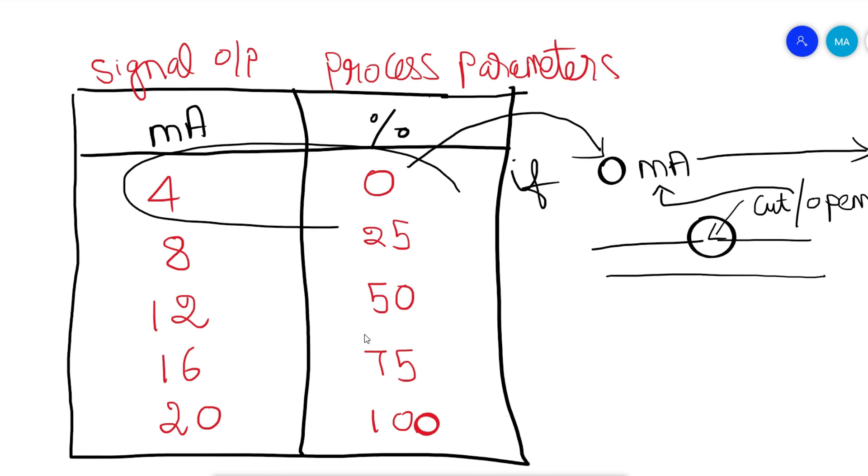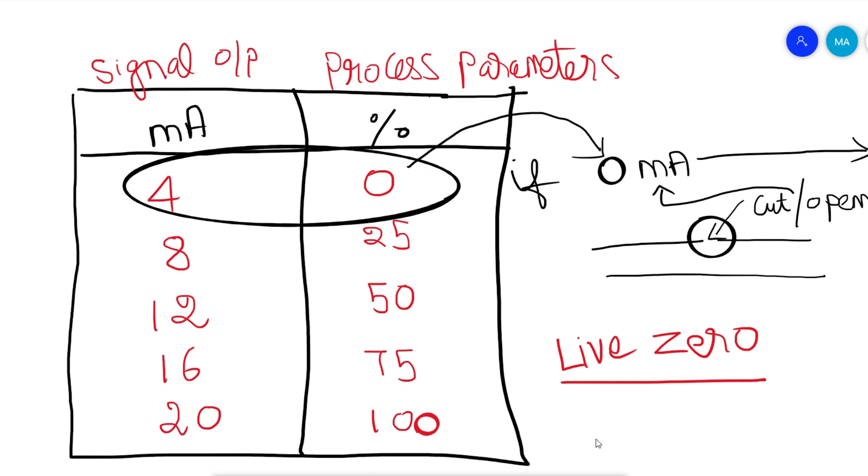This is called the live zero concept. It is easy to detect if the signal wire is broken. With zero milliamps, we would be unable to identify whether that is a signal or a wire break. This is the main reason to use 4 to 20 milliamps signal - the live zero concept.